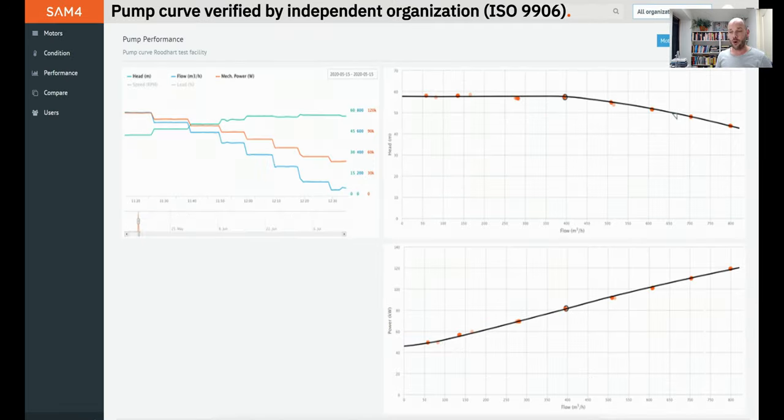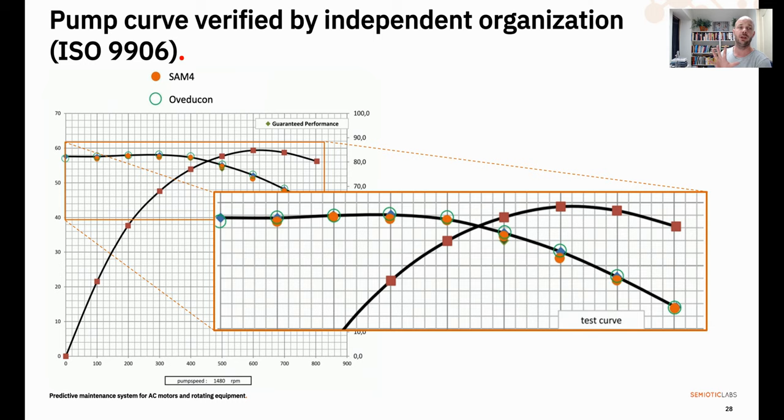Now you may wonder — all very well and good, but it's only useful if it's accurate. And frankly, it is. We tested the accuracy of our solution in an ISO 9906 test setup, and as you can see, the observed working points track that curve very, very closely. We also asked our friends at Oveducon — they call themselves pump idiots, in a gentle fashion, and they are really in love with pumps. They tested our technology using that same ISO 9906 setup, and as you can observe, the work points we calculate track the golden-standard work points very, very closely.